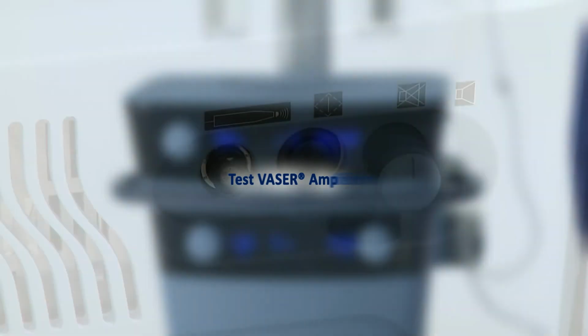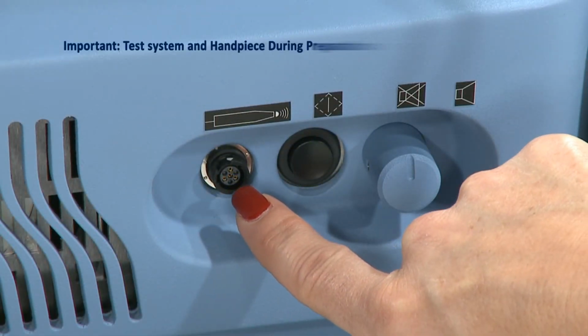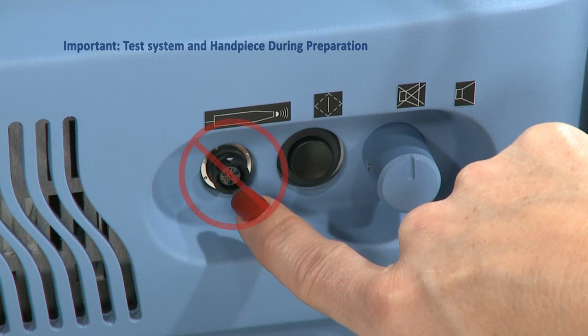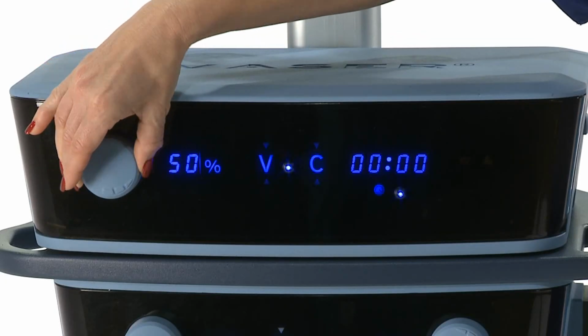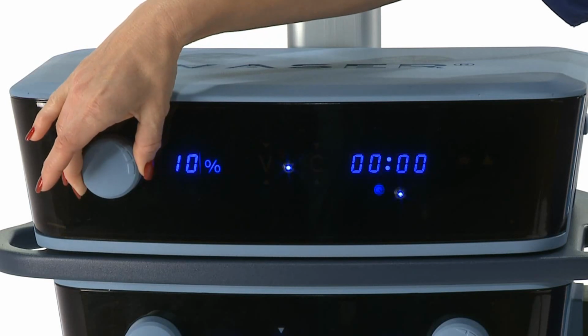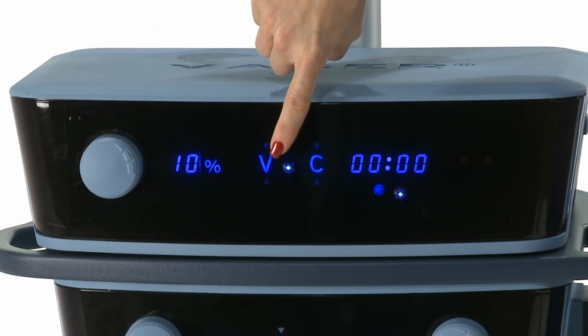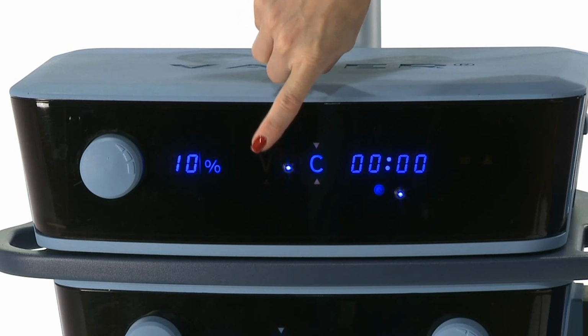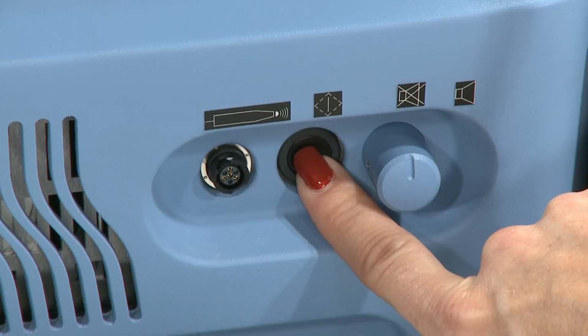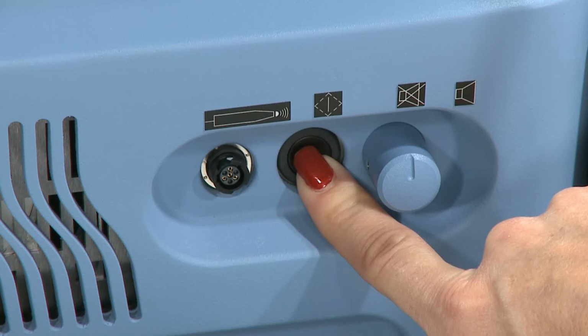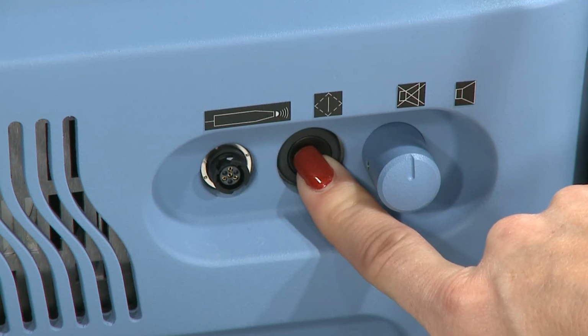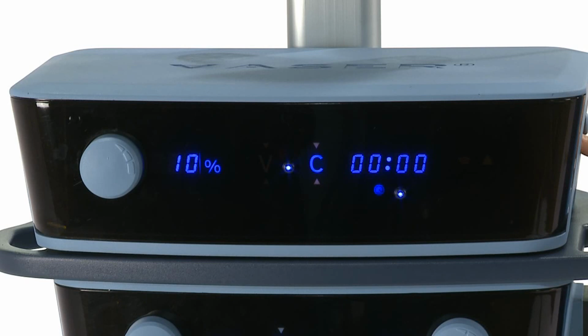It is very important to ensure the Vaser amplifier and the Vaser handpiece are working properly before the patient arrives. To test the amplifier, ensure that the Vaser handpiece is not connected to the amplifier. Set the amplitude to 10%. Set the mode to C, continuous. Press and hold the Vaser test switch for at least 5 seconds. You should hear an intermittent beeping and see the ultrasonic wave and a fault symbol illuminate on the amplifier.